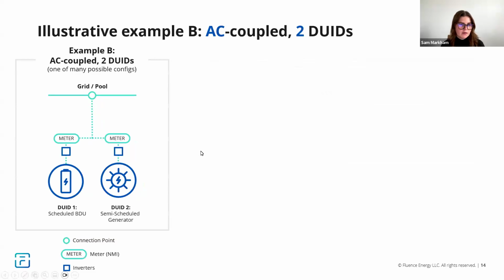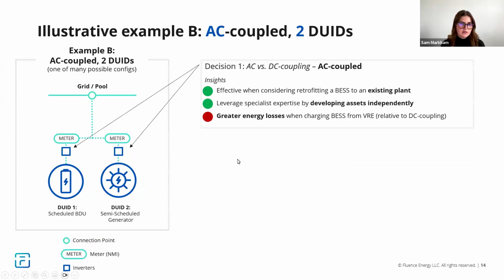So on to example B. This is AC coupled, where there's essentially 2 separate assets, each with their own inverter. This can be effective when considering retrofitting BESS to an existing plant, and can also be helpful if you're looking to leverage expertise by developing those assets independently. However, AC coupling can face greater energy losses when charging the BESS from the co-located solar plant rather than from the grid, relative to DC coupling, because of the conversion from DC to AC and then back.